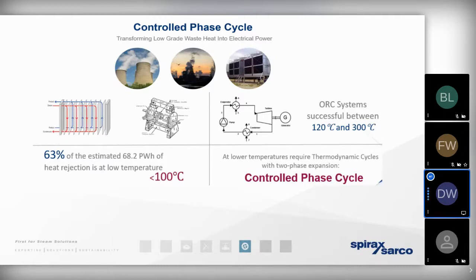So one of the problems is that not only is this a waste of heat energy, but quite often this waste heat energy then has to undergo some form of cooling before it can be disposed of, which is going to further add to the costs. For example, if it has to be put across a cooling tower.